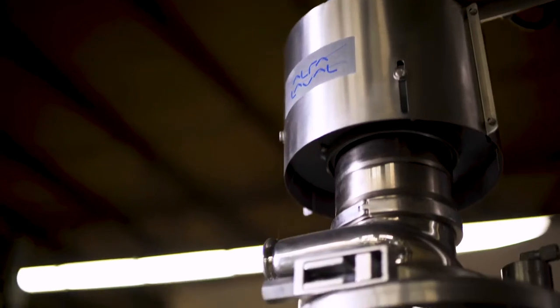Gasketed plate and frame heat exchangers or tubular heat exchangers have no moving parts, so I'll refer to them as static heat exchangers. And we can design them, and Alfa Laval does an amazing job to design them, to optimize them, but at some point they reach their limitation. You get to the point where you physically need to have something mechanically removing that fouling layer, and that's where the scraped surface heat exchanger comes in.